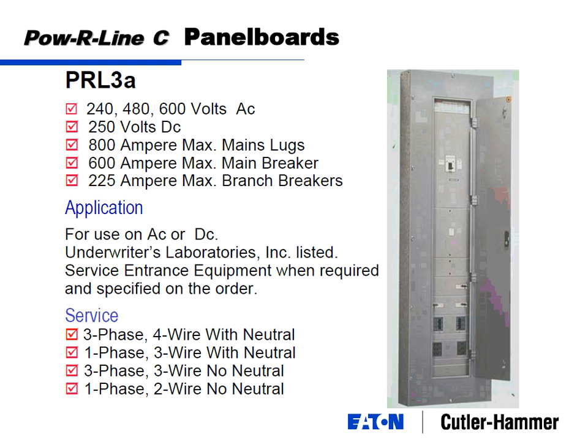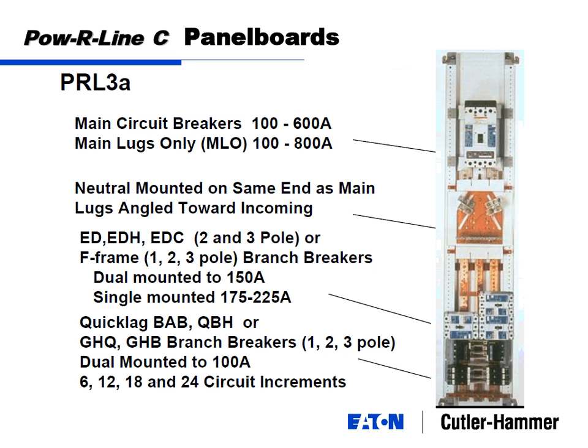And the big key here is you can also get the 225 amp max circuit breakers. So before I was limited to 100 amps, Powerline 3 gives me up to 225 amps. And what that can look like, or the benefits of something like this, you can see here's what the actual panel chassis looks like, much different than the first two. Still got a main breaker, could be main lugs out there.